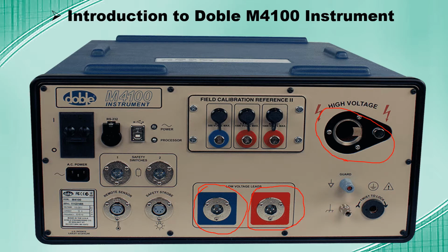The third point was to connect at the earthing point of the CT. That earthing point cable will be connected over here in the kit. This cable is called the earthing cable. Now these are the three main cables that we will be using to measure tan delta and capacitance in a CT.